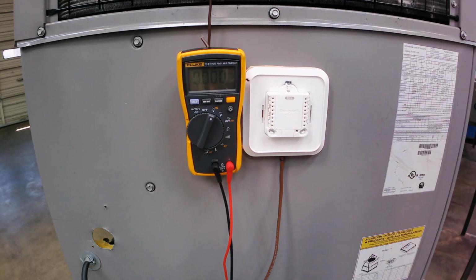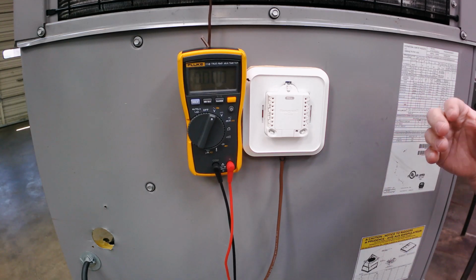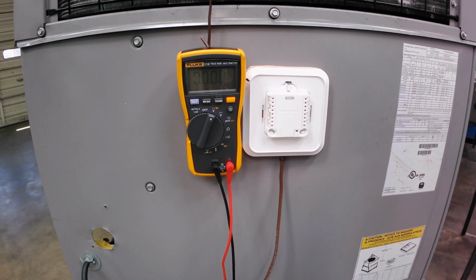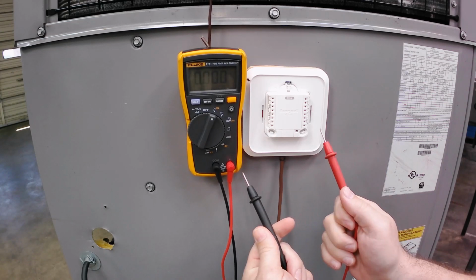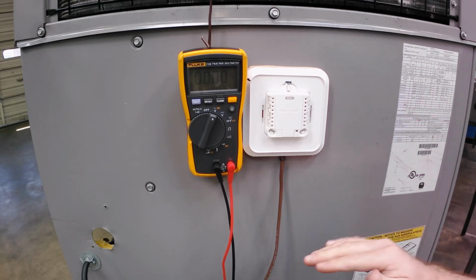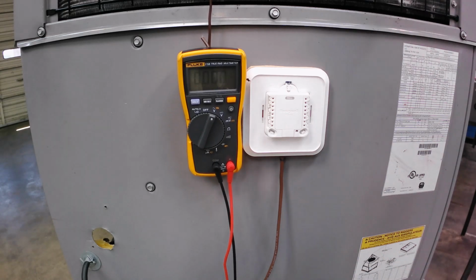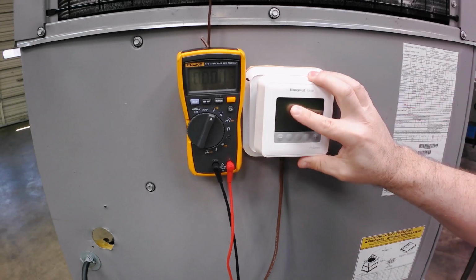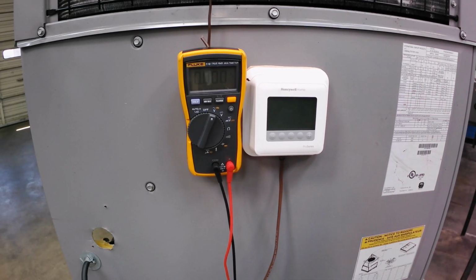So when you go to a thermostat, if you want to see if it has the capability to work, check power, check R and C with your leads, with your meter, and if you have 26 volts, that's enough. I would put the faceplate back on and be done with it.